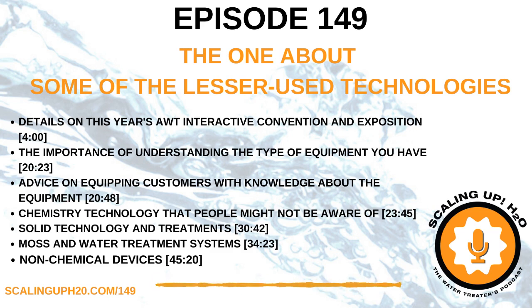You may say, I want to spend $10,000 for a controller, but you have so many more options and flexibility, and you can really dial that program in, even to the point where it turns on the chemical pump or turns it off, sends you an alarm because of a high conductivity or a low conductivity, a low drum level. You may be running low on a product.